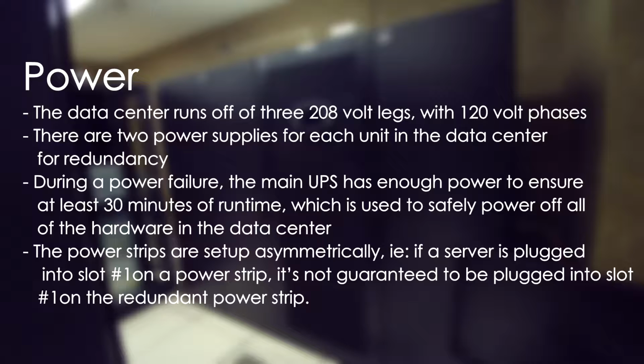During a power failure, the main power supply has enough power to ensure at least 30 minutes of runtime, which is used to safely power off all the hardware in the data center. The power strips are set up asymmetrically, meaning if a server is plugged into slot 1 on the power strip, it is not guaranteed to be plugged into slot 1 on the redundant power strip.